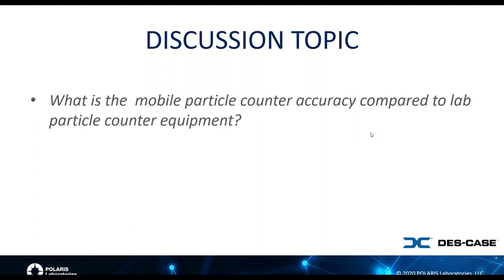No, in fact, it just occurred to me that the mobile particle counter could actually be used in conjunction with the portable filter cart. If you see that your particulate trend is increasing, you can use the portable filter to try to get some of that dirt out of there. Exactly. It's a trending tool. It's not a replacement for lab analysis.